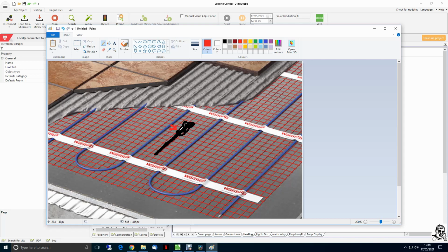At the time we have 28 degrees in here, near the heater the temperature is a bit higher, and it depends how thick your floor is. If it's very thin, the transfer will be faster, but if it's thicker, you need to run it and check if 28 degrees is right for you. At the beginning I set it to 35 degrees, and in half an hour we were boiling inside the house, and in some cases you can go even lower.